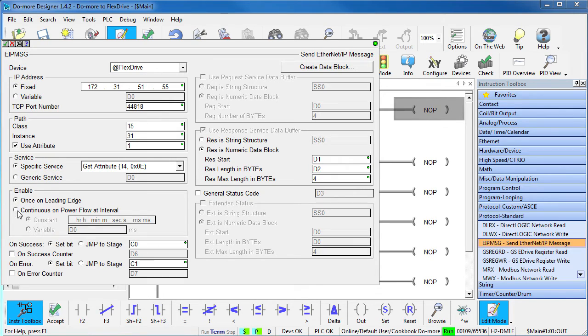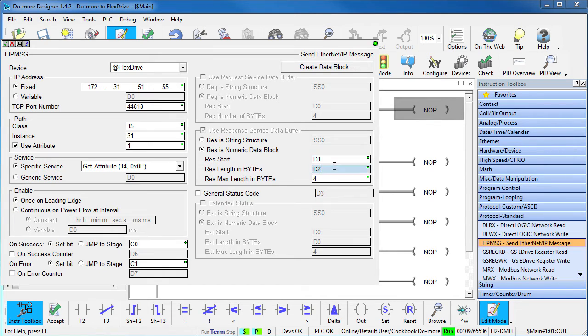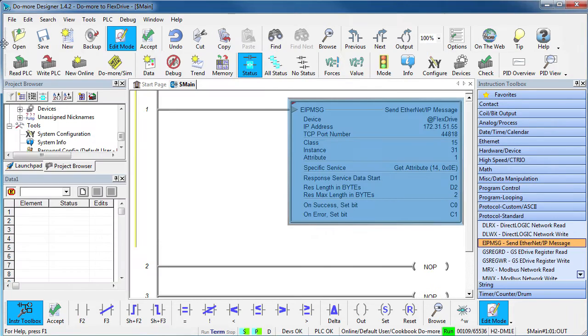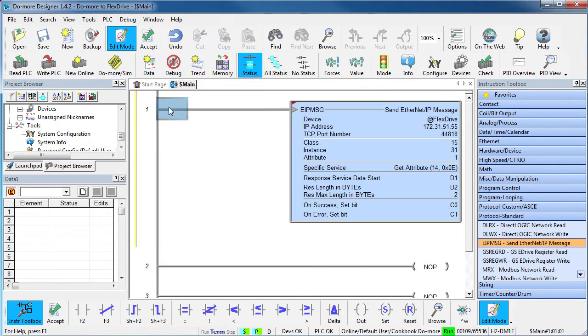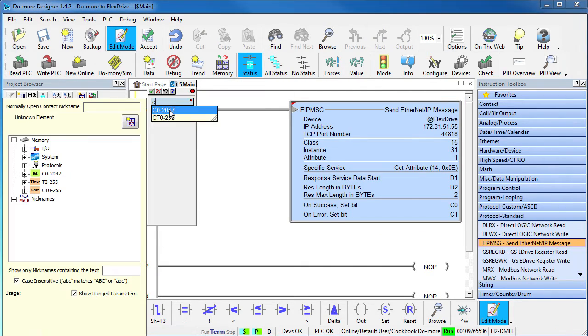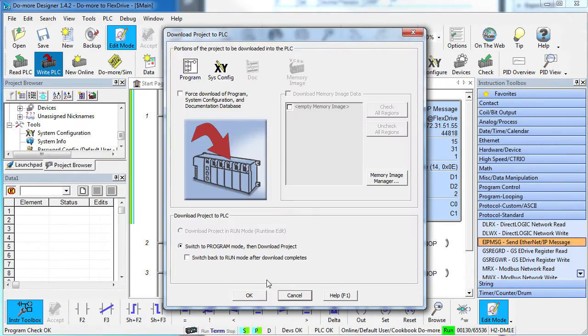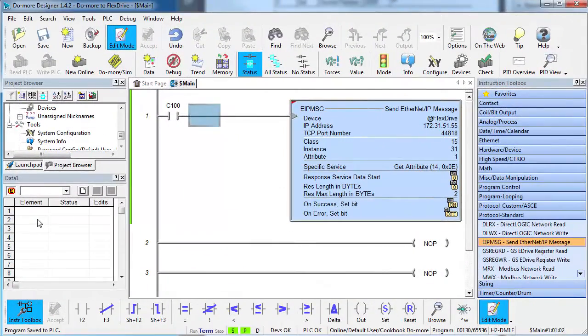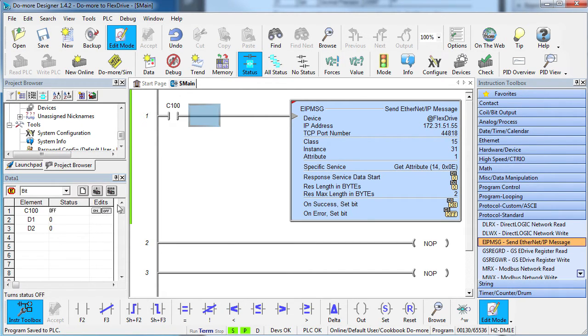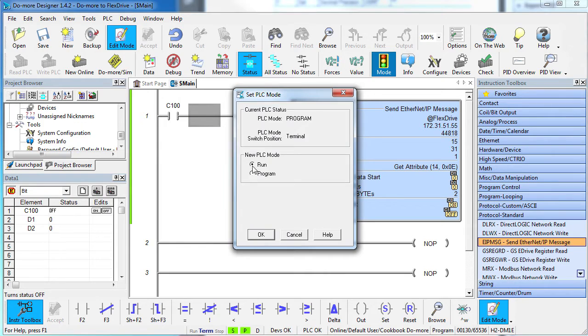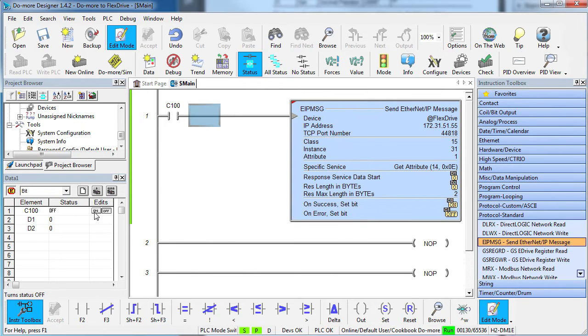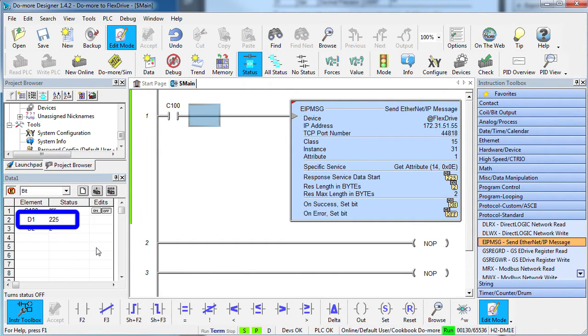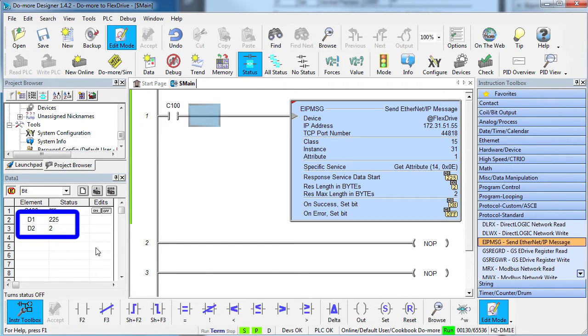We'll enable this on an edge. Set these bits on success and error. And put the response here, which I happen to know is a 16-bit unsigned result – I'll show you how I know that in just a minute – which is 2 bytes max. Let's add a control bit so we can enable this instruction and transfer the project. Let's bring up a data view and monitor the result which we put in D1 and the result length which we put in D2. Let's also add the control bit so we can activate the instruction. When I toggle that control bit, I see the request was successful and the nameplate voltage is 225 volts. And that 2 bytes were returned. Perfect.